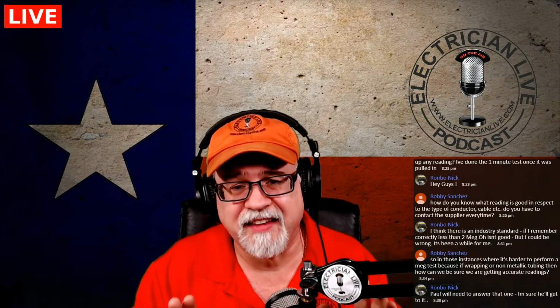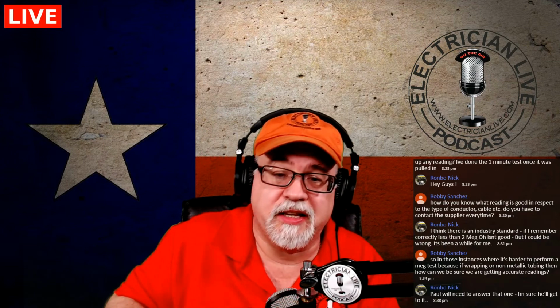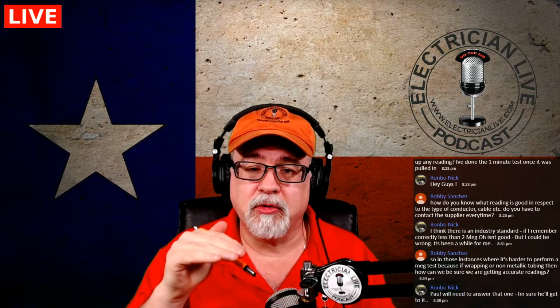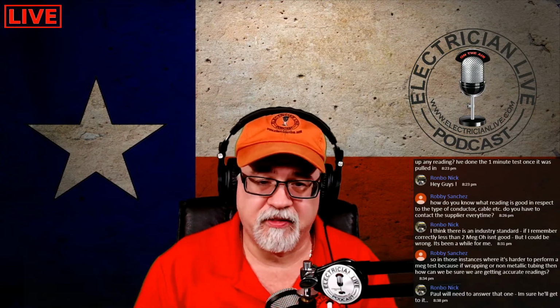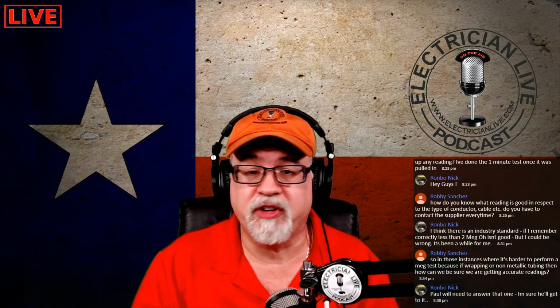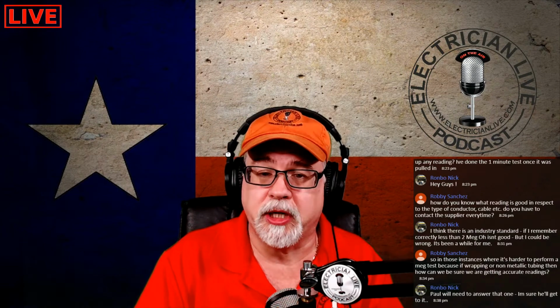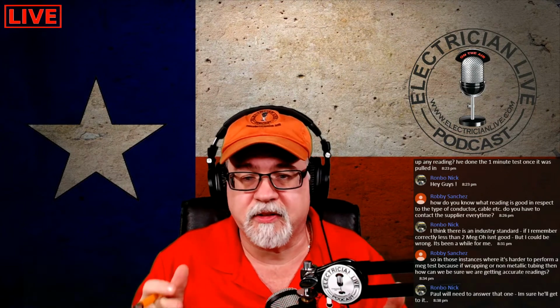Okay, now, with that said, let's shift gears to what's called the maintenance standard for NETA. Now, say everything is PVC, and let's say you get these readings. These are predictable readings based on the conditions that it's being placed in. You could mark those down, and you use those values as your measure point for your next test, which might be 6 months from now, might be a year from now, however your test is, and you plot it out. So then those initial readings that you get can be beneficial to plot a curve with potential breakdown of conductors or cables after installation. So you could have a position where you had something that was 100 megaohms, and then 6 months from now, it drops down to 12 megaohms.